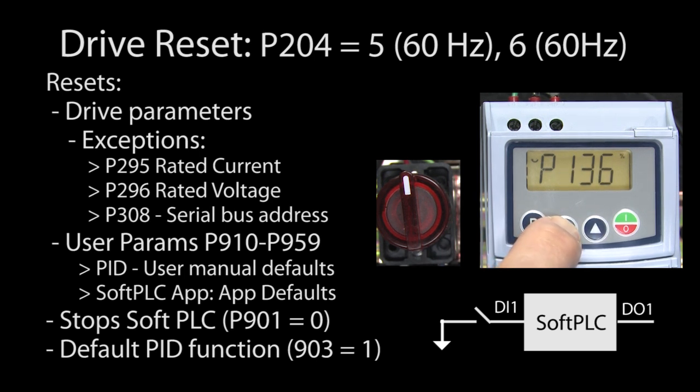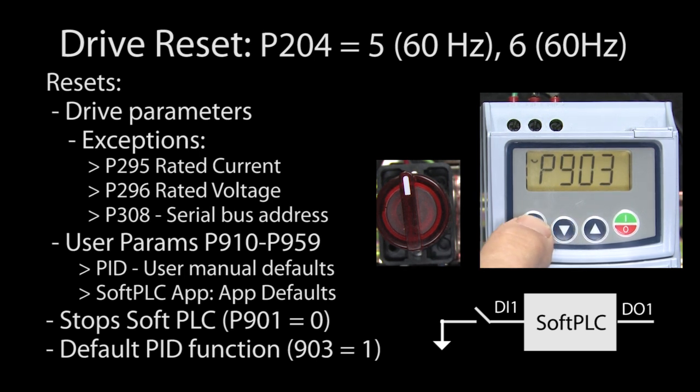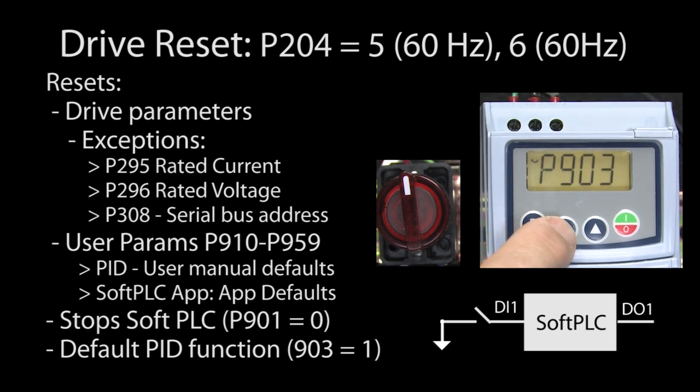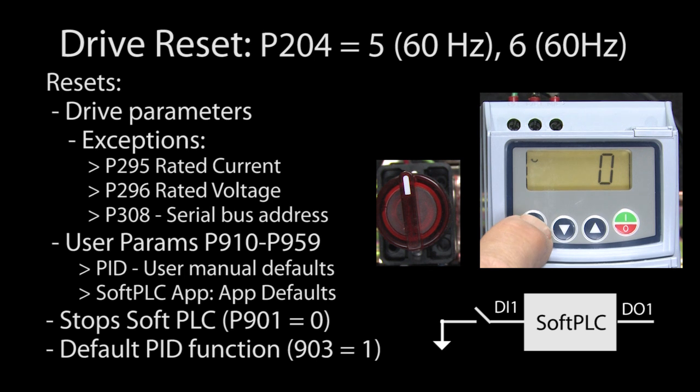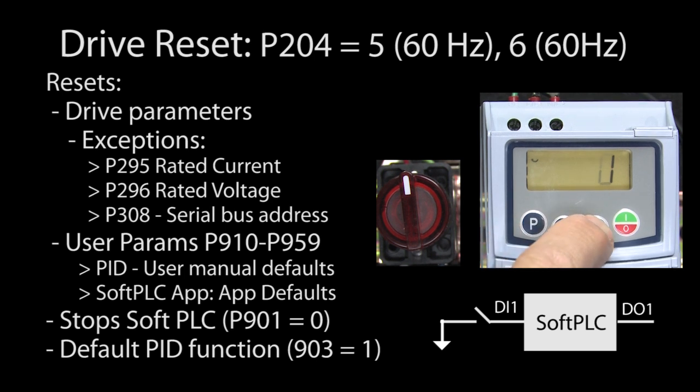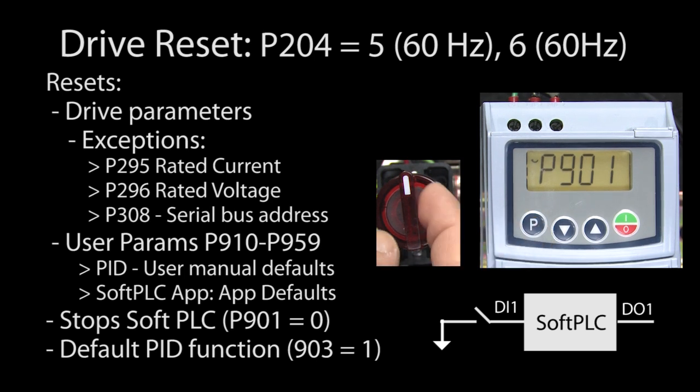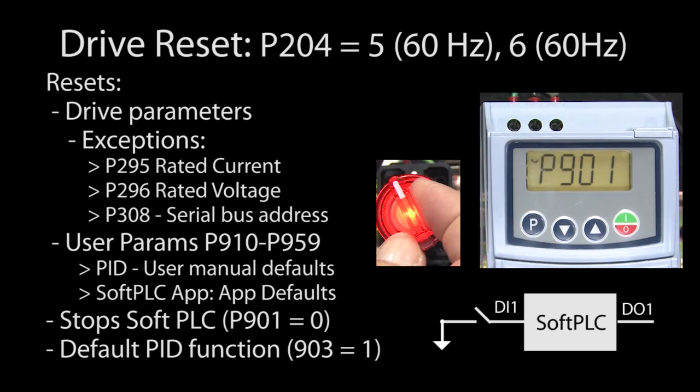Now, if I go to parameter 903, I see it got reset to the built-in PID function. I'll change that back to my soft PLC app. And parameter 901 after the drive reset says the soft PLC has stopped, so I'll change that back to run the program. And sure enough, my switch and indicator are working again - perfect.